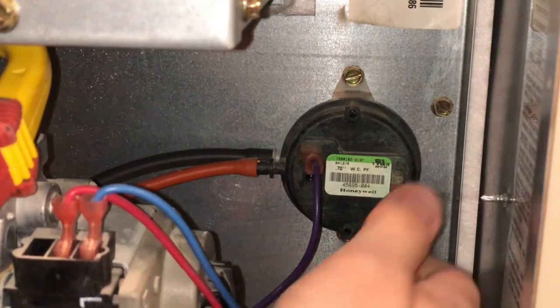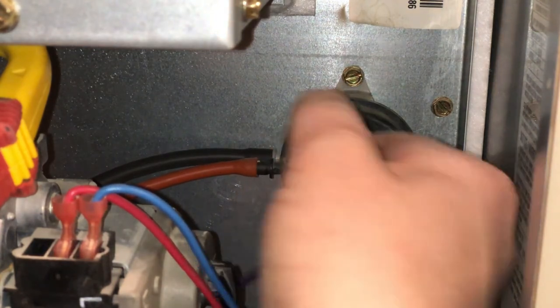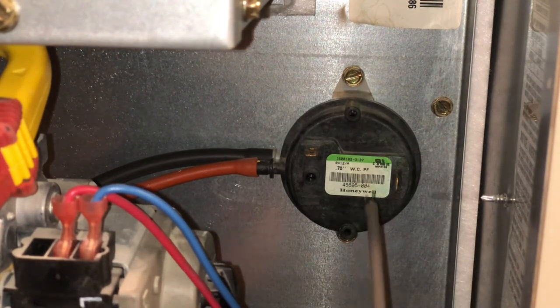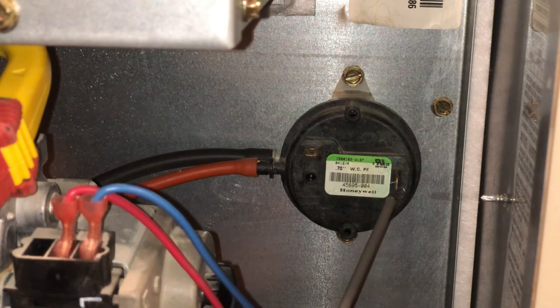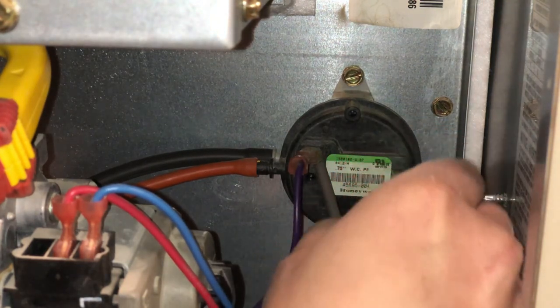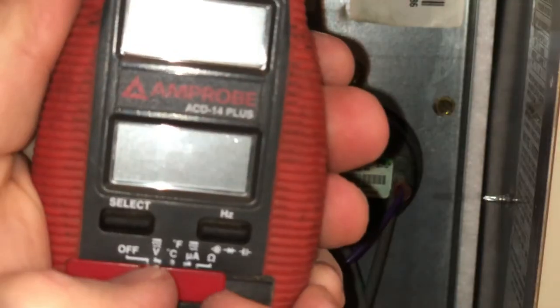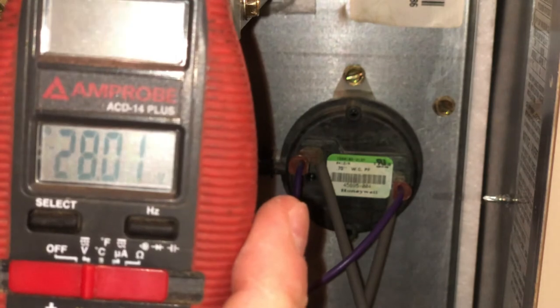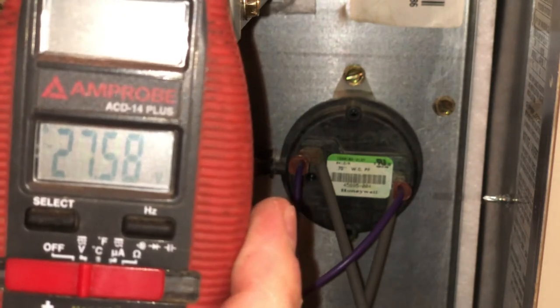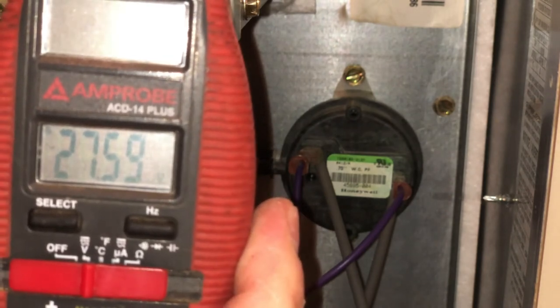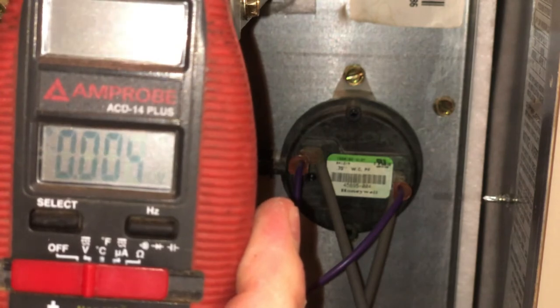You can test to see if the switch closes electrically by putting your meter test leads on the two electrical connections for the pressure switch. Set your meter to read 24 volts AC. If the power is on and the switch is open, you should see a potential across those two terminals of about 24 volts. And when the switch closes, you should see that potential drop down to zero.